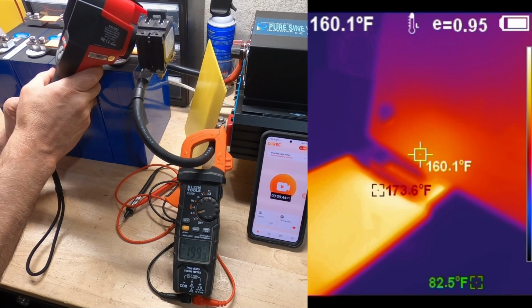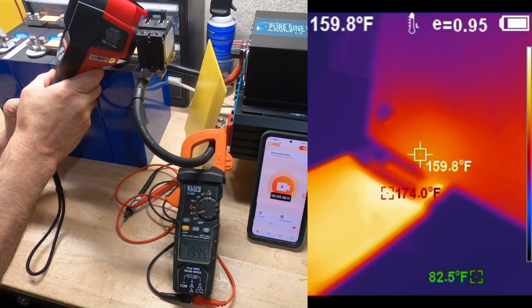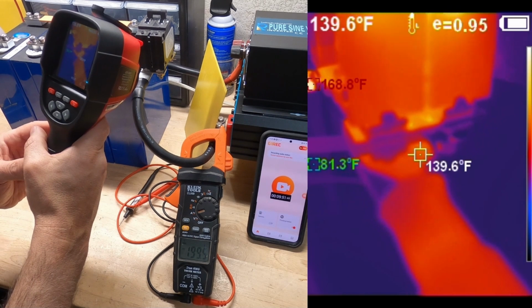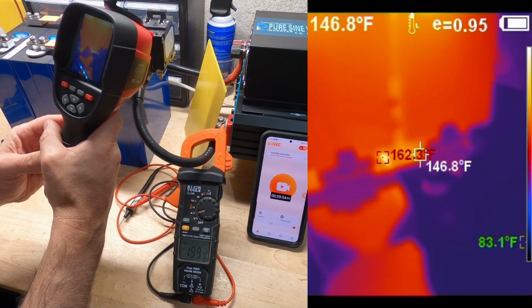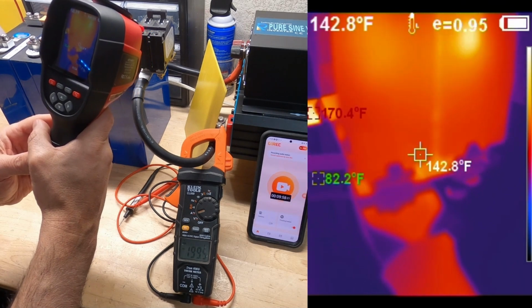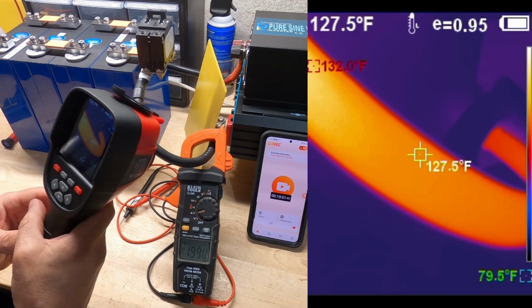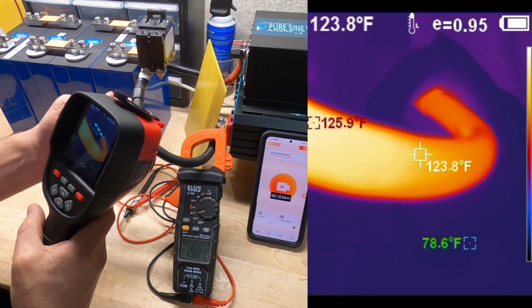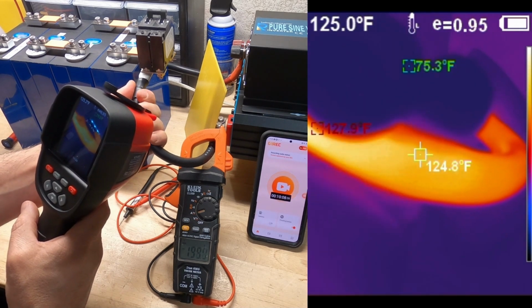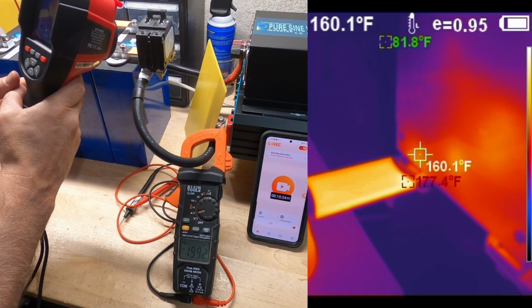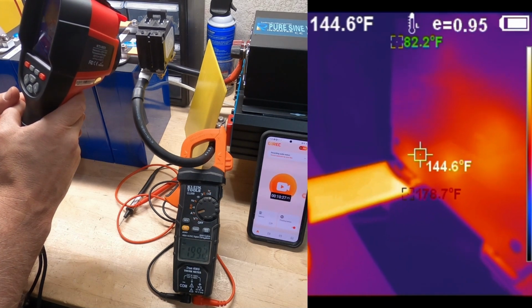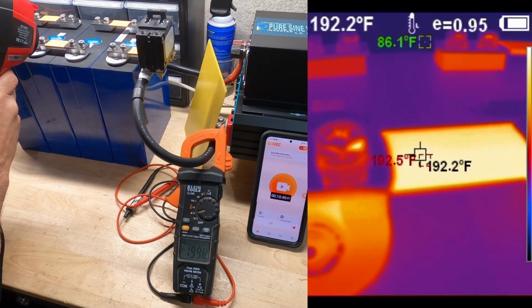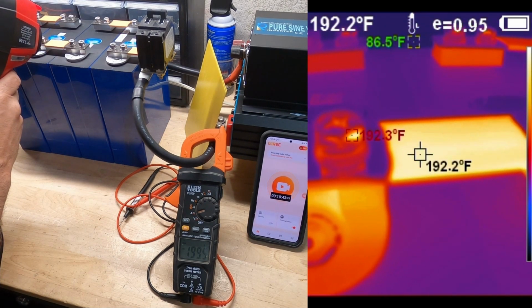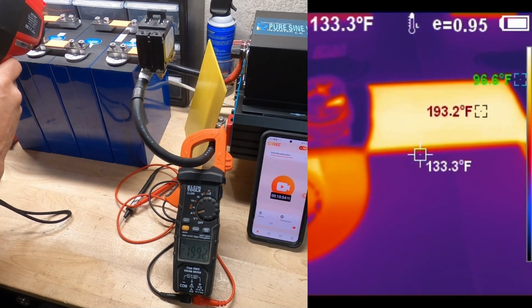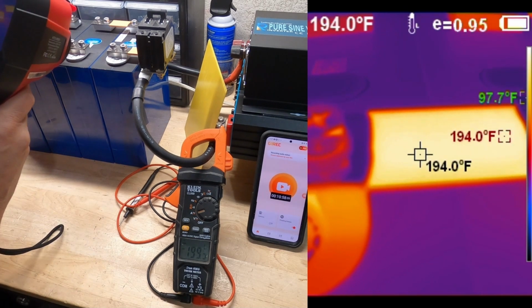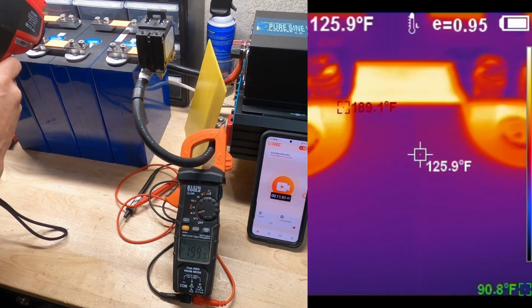We're running about 90% duty cycle on this breaker. We're almost 10 minutes. Our cable is still sitting at 130 degrees. So I'm pretty impressed with the cable. Alright, so there's 10 minutes, and I think everything's sort of leveled off, where it's not really going to heat up anymore, given our ambient temp. Look at that bus bar, wow, 192. That's a little hot for the bus bars, that definitely is too hot. I'd be more concerned with those than anything.